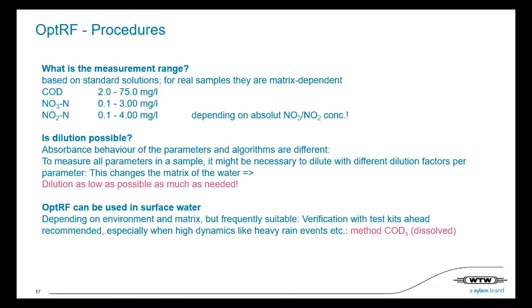For nitrate, we are between 0.1 and 3.0 milligrams per liter — a bigger range — but you have to consider that if there's a lot of nitrate, nitrite in the same range is covered by nitrate. So actually we talk mainly about COD and nitrate.